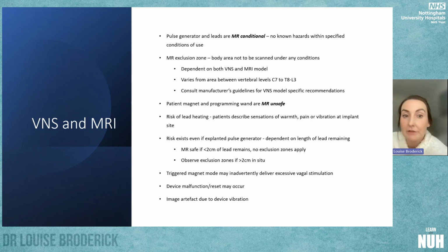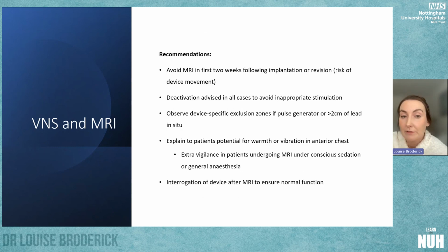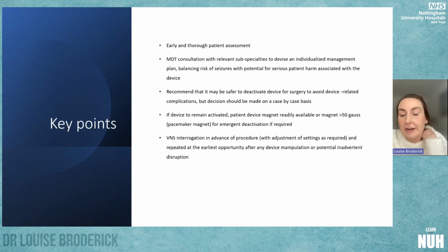The risk of heating of the device exists even if, as I mentioned, the pulse generator has already been explanted. So if there's less than 2 centimeters of the lead remaining in situ, the device is MR safe, no exclusion zones apply. But if greater than 2 centimeters of the lead is in situ, or any part of the pulse generator is in situ, the device becomes MR conditional. There is a risk of triggering magnet mode by the MRI, causing excessive vagal stimulation during the scan. The device may malfunction or reset, and of course, image artifact may occur. So MRI should be avoided in the first 2 weeks after implantation. The manufacturers advise to deactivate the device in all cases to avoid inappropriate stimulation, observe the device-specific exclusion zones if more than 2 centimeters of the lead is in situ, and interrogate the device afterwards.